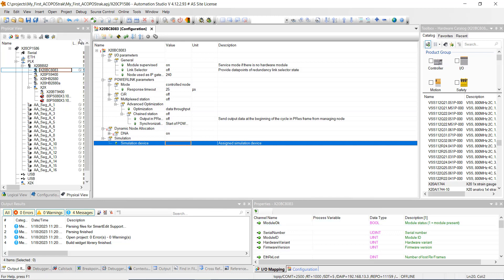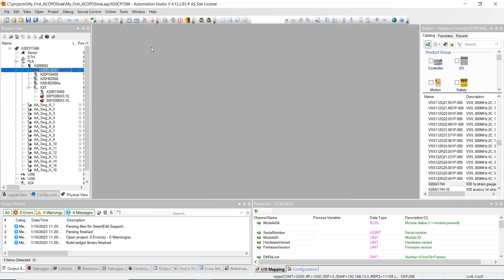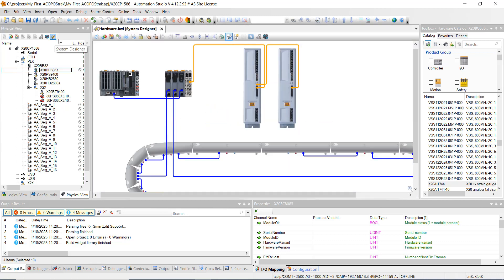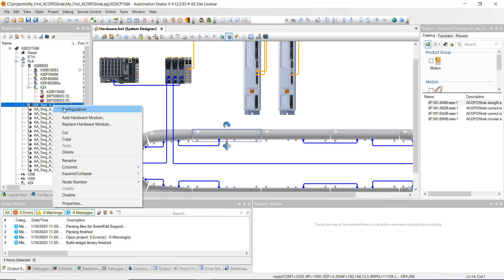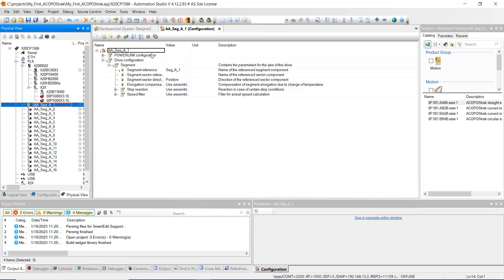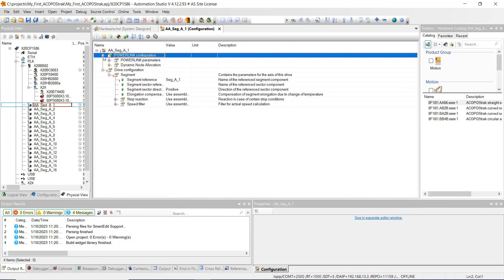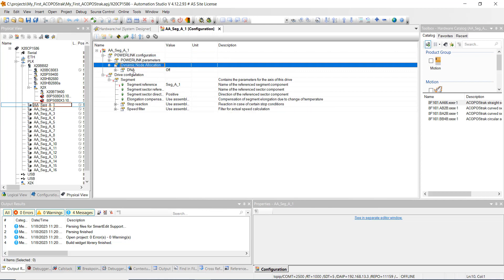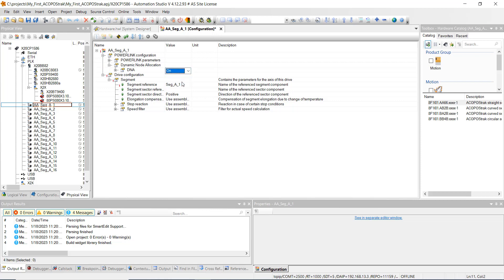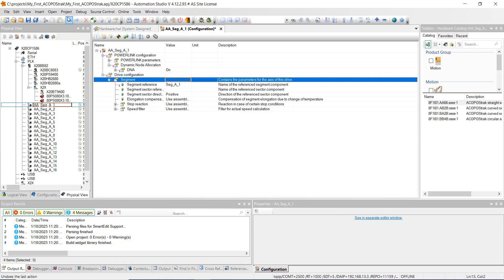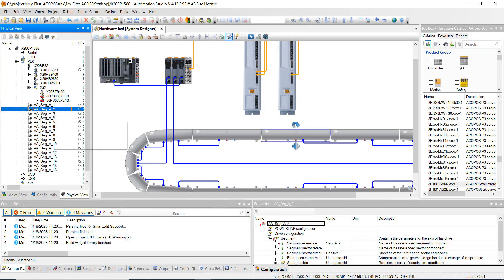Then go back to each segment. Open up the system designer and right-click on the first one. Go to Configuration, then under PowerLink Configuration hit the plus sign, and under Dynamic Node Allocation hit the plus sign and change DNA to on. We're going to do this for all of these — hit Save All, close it, go to the next one and do the same thing, all the way down through 16.